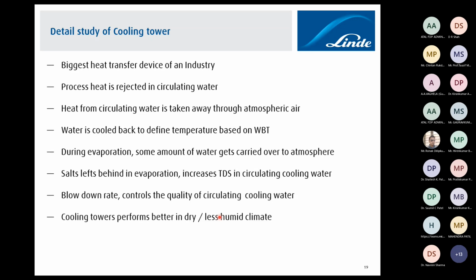So cooling tower, as you know, performs very well in dry and less humid climates. Basically in winter you will find less humidity and dry air. In summer you will find some humidity because it is close to the monsoon region, and in monsoon it performs a little bit poorly because there is a lot of humidity and dryness is not available, so the air is already saturated and it has to perform a range of temperature reduction, which is sometimes difficult.